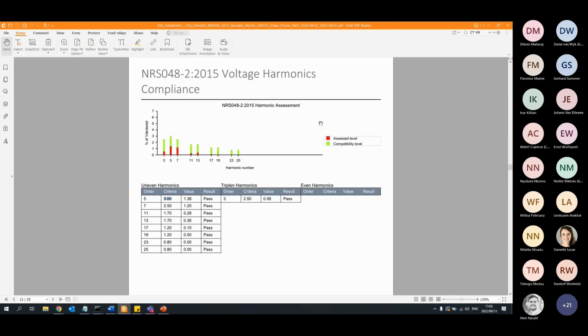Just want to check with you, is there a way to filter out time-based analysis of, let's say, the harmonics, so that one can then start filtering between what was attributed by PV, or by the inverters, during the night times and so on? Is there that ability to do that? So if I, sorry? The trend, will it trend over time?